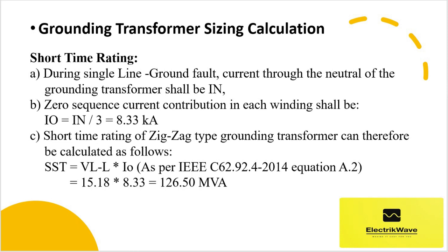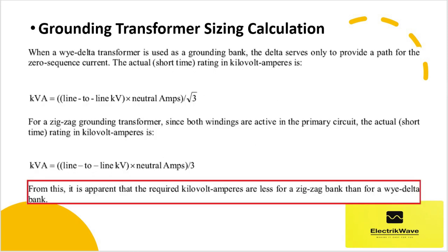Sst = line-to-line voltage × zero sequence current, as per IEEE C62.92.4-2014, equation A.2, which comes out to: 15.18 kV × 8.33 kA = 126.50 MVA. Note that there are two different formulas to calculate the short time rating for a Y-delta transformer and a zigzag type grounding transformer, as shown here.